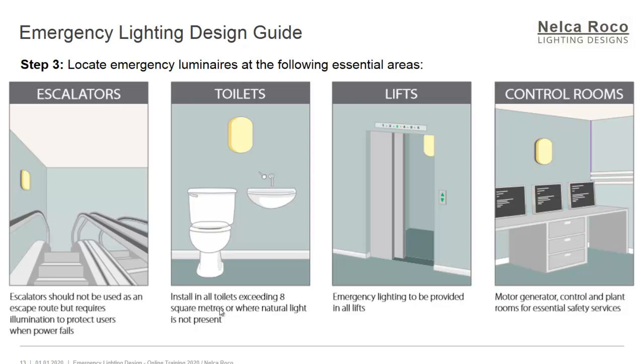For toilets: install emergency lighting in all toilets exceeding eight square meters, or where natural light is not present. For every toilet or cubicle not exceeding eight square meters, you should provide a dedicated emergency luminaire. For lifts: emergency lighting must be provided in all lifts — sometimes it is included by the lift manufacturer or supplier, but if not, you need to add a dedicated emergency luminaire. Control rooms, motor generator rooms, and plant rooms for essential safety services should also have a dedicated emergency luminaire.